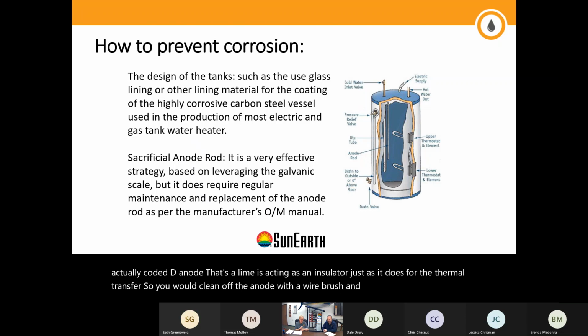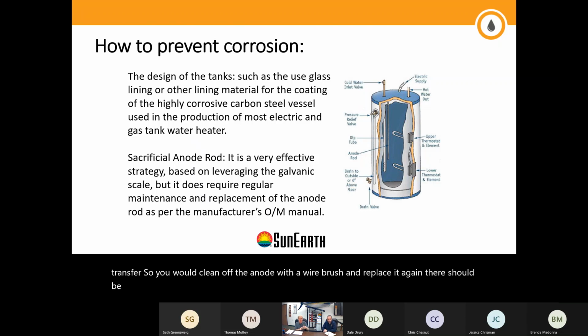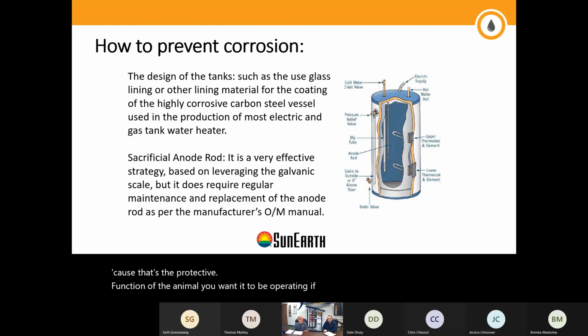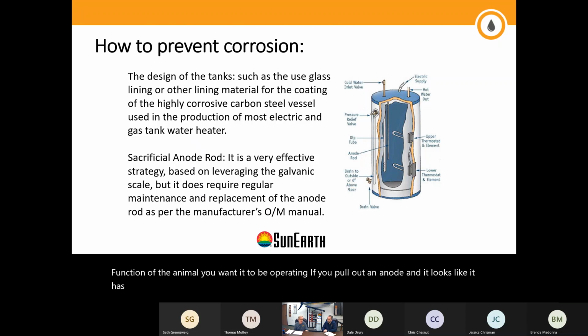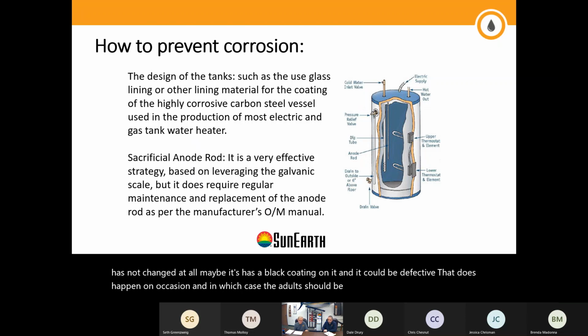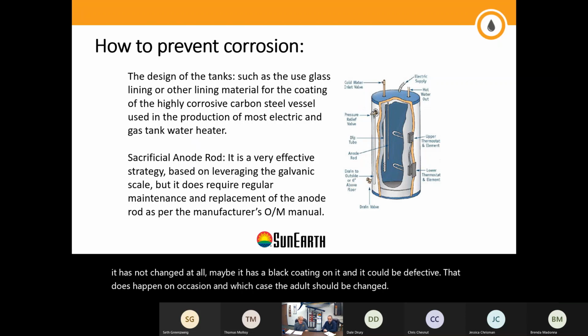Again, there should be some indication that the anode is being dissolved by the water, because that's the protective function of the anode. You want it to be operating. If you pull out an anode and it looks like it has not changed at all, maybe it has a black coating on it, the anode could be defective. That does happen on occasion, and in that case the anode should be changed. Otherwise, the anode's not doing its job.